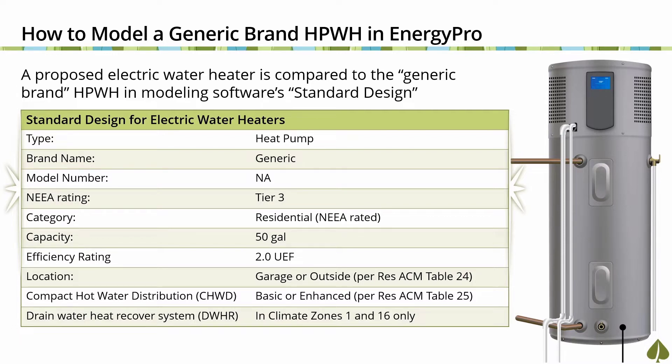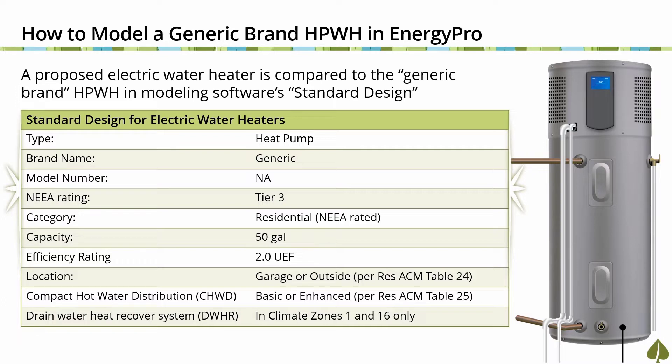NEEA Tier 3 heat pump water heater with a capacity of 50 gallons. UEF rating of 2.0 with a unit located in either the garage or outdoors, depending on the climate zone the project is located in. Please refer to Table 24 in Chapter 2 of the Residential ACM Manual for further information.